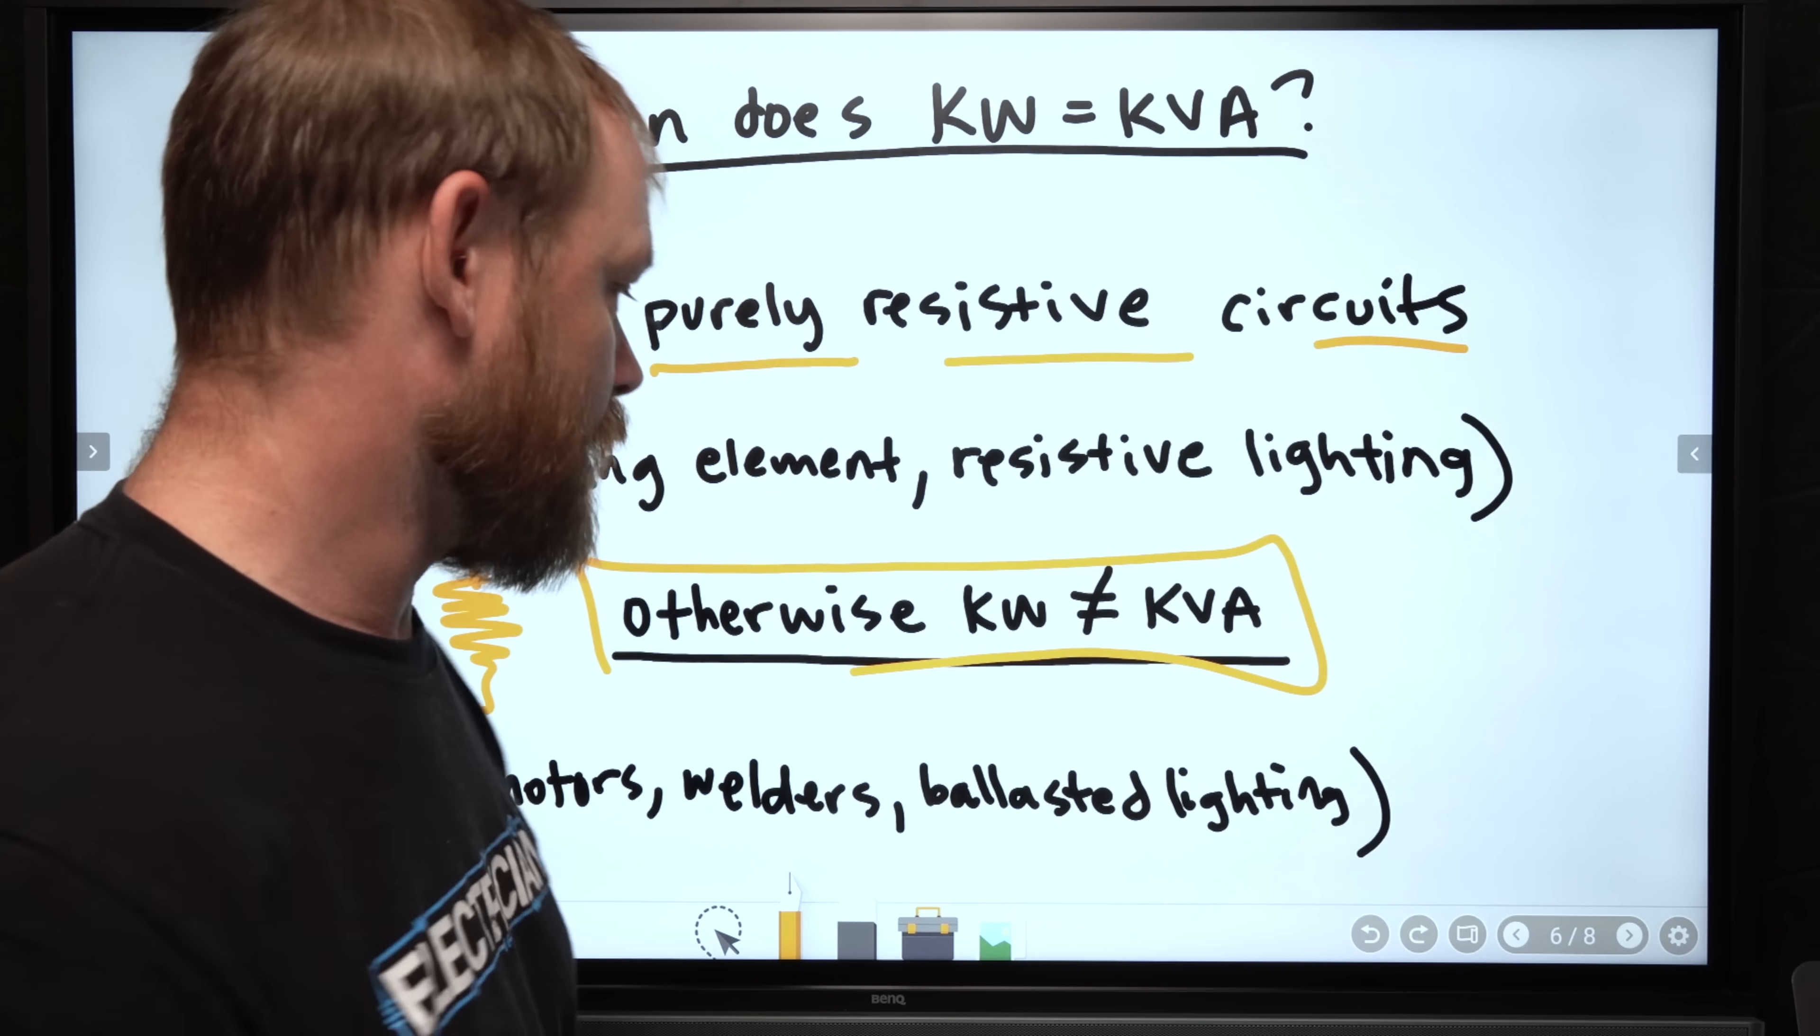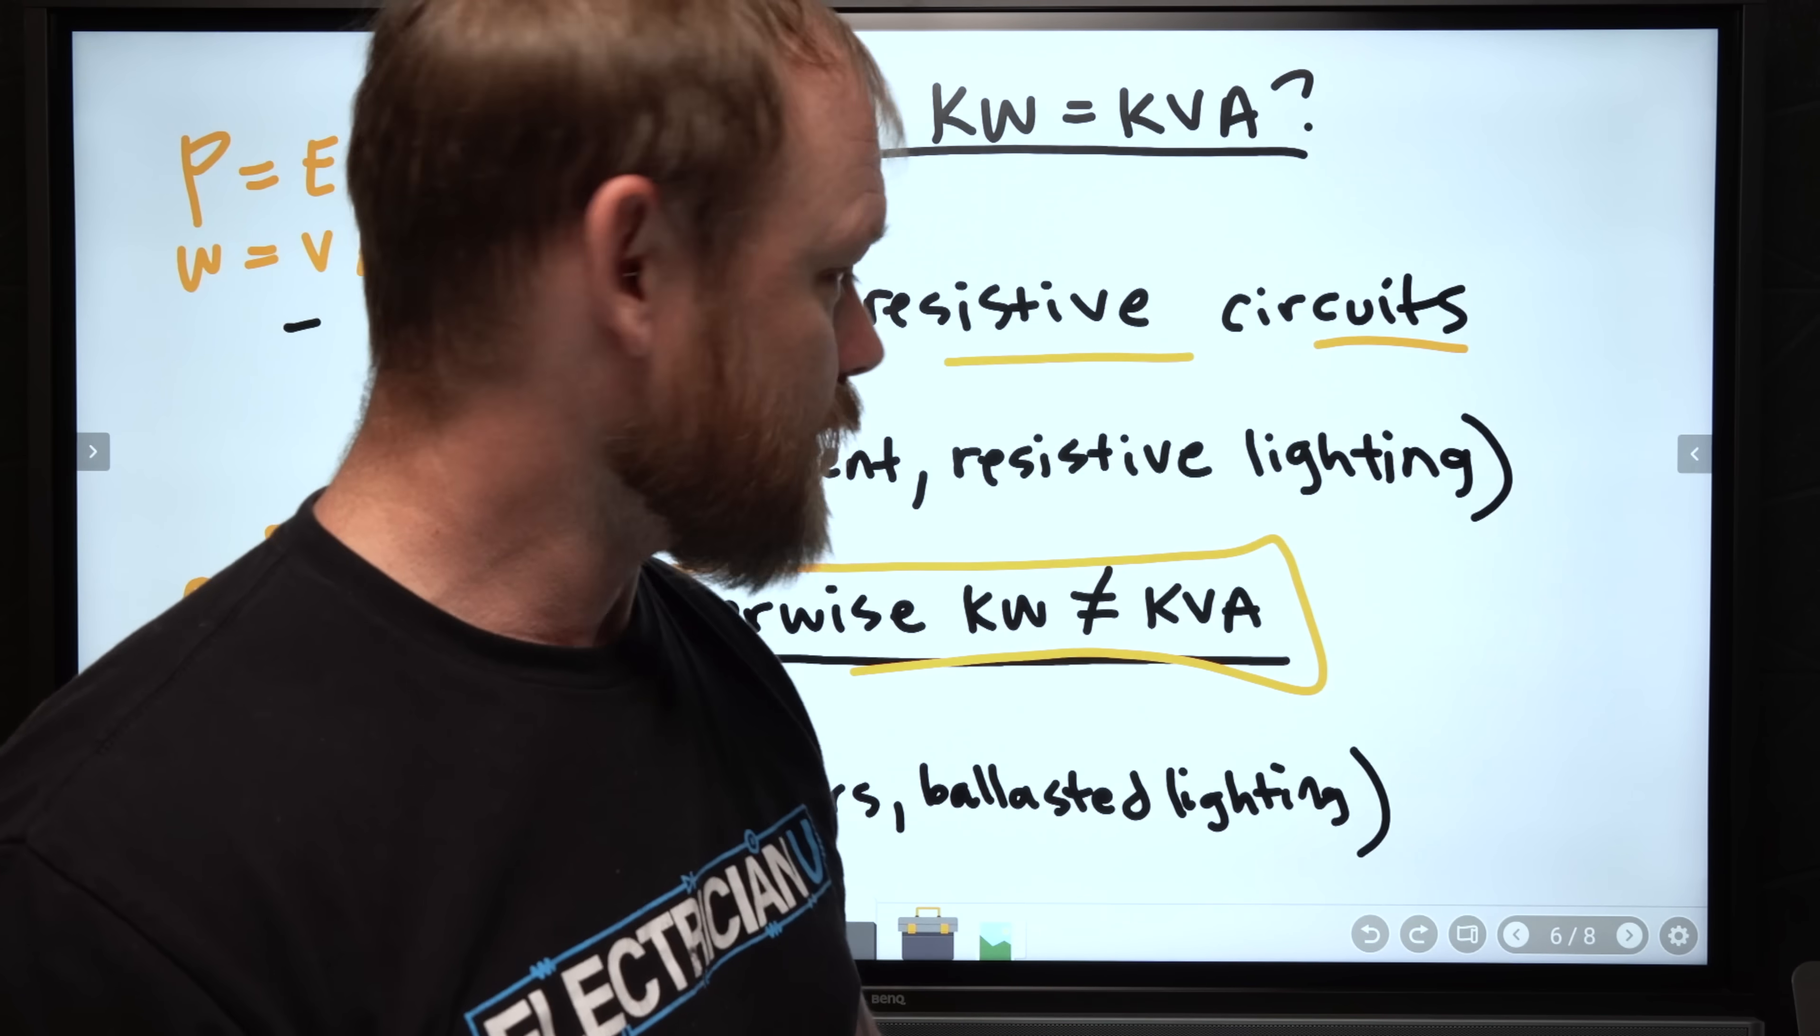But everything else, otherwise every single other thing in the world, any lights that have ballasts, so like compact fluorescent, fluorescent, LEDs, every kind of bulb, high pressure sodium, mercury vapor, all of those are going to be some kind of ballasted light which is going to have a reactive component to it. So your KW is not going to equal your KVA. If you've got a welder, motors, transformers, any of that, the rest of the industry, basically.